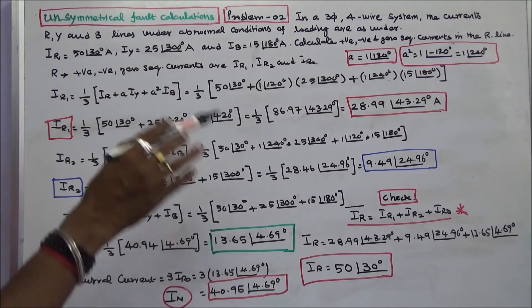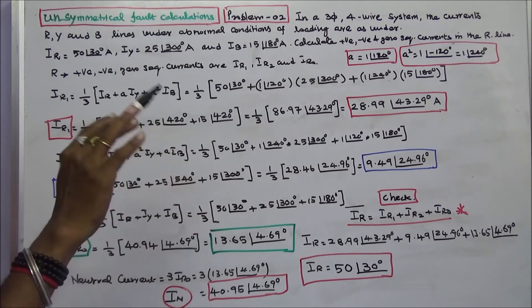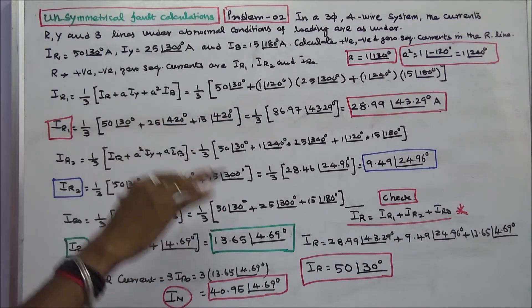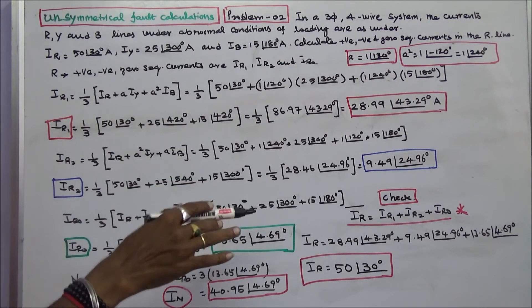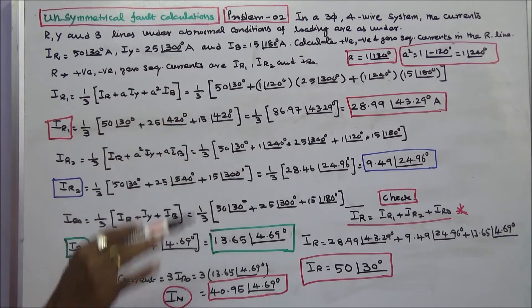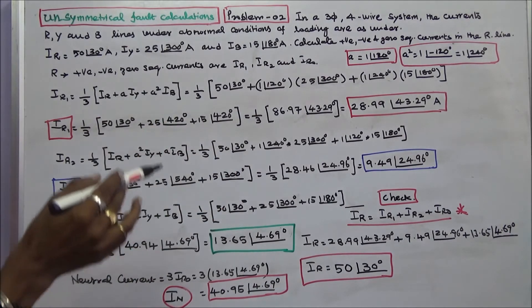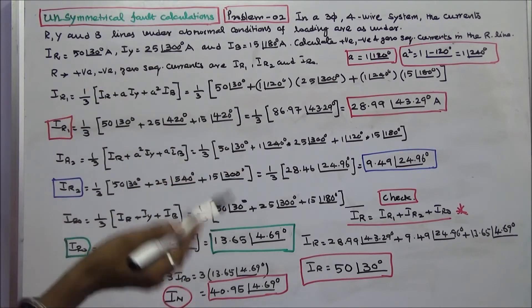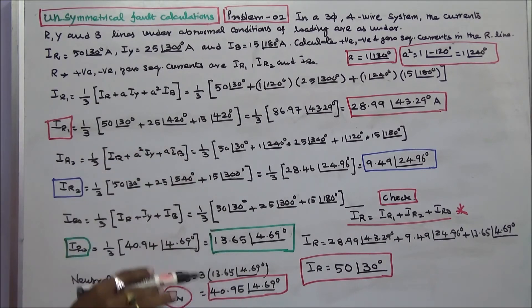In a balanced system, the zero sequence current and the negative sequence current are zero; only positive sequence current exists. If the system is unbalanced, the zero sequence and negative sequence currents will exist, so the neutral current is not equal to zero. The neutral current is IR plus IY plus IB, or 3 times the zero sequence current. With this I conclude my lecture. Thanks for listening.